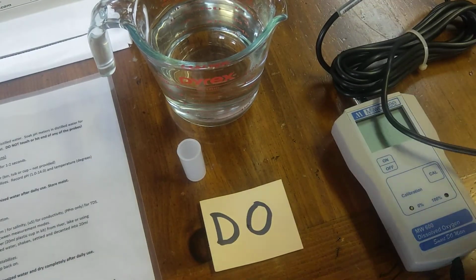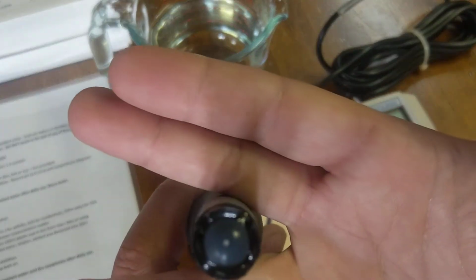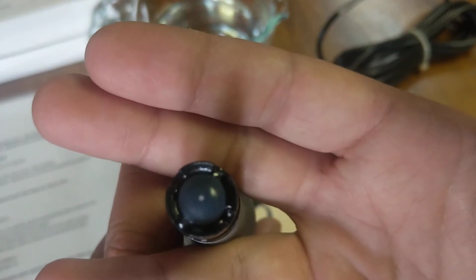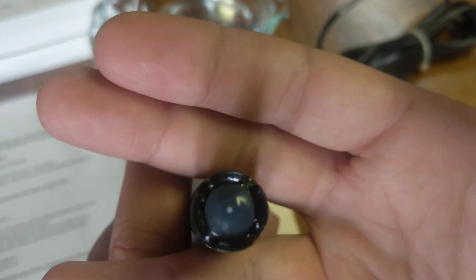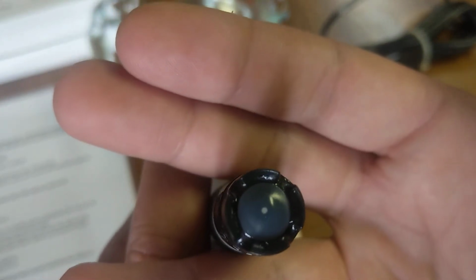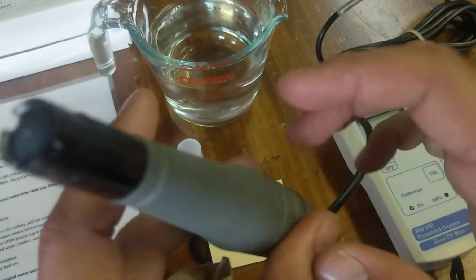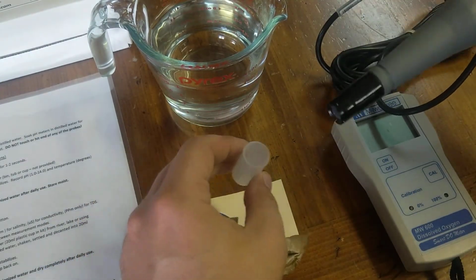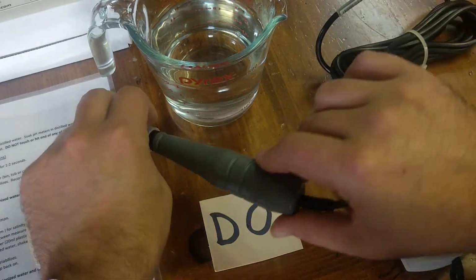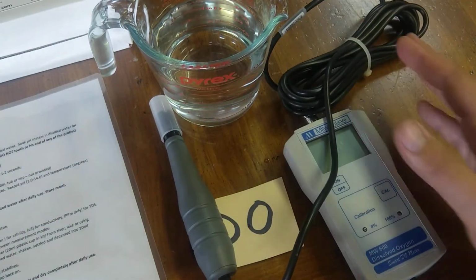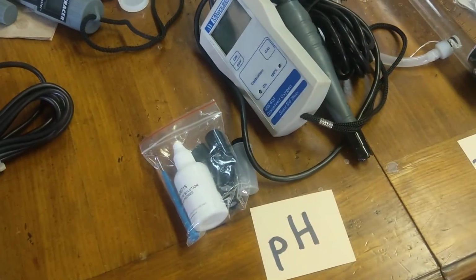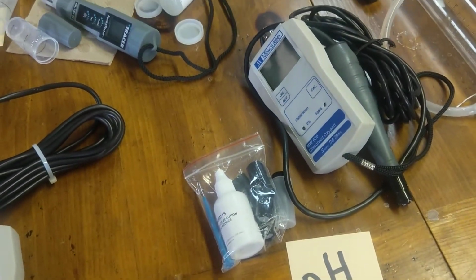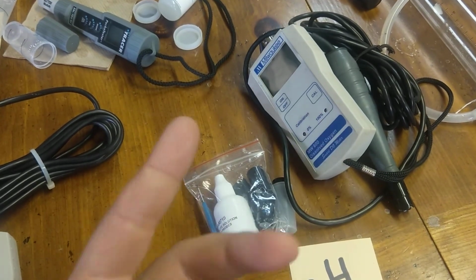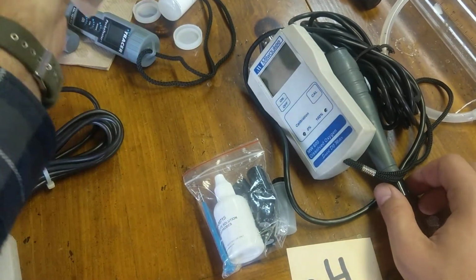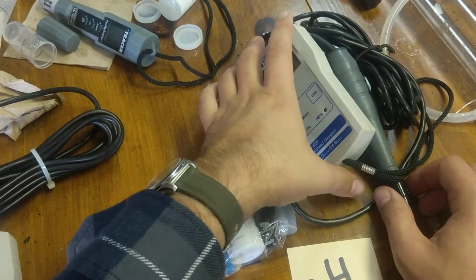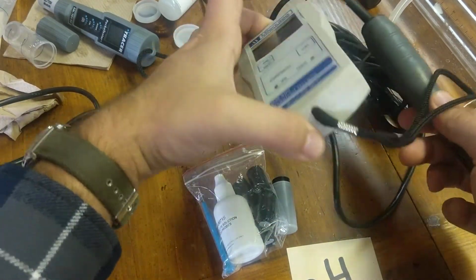Now, just for general maintenance, you want to make sure there's, again, no bubbles on the end here that is filled with that fluid. That fluid is necessary in order for it to continue. There's no bubbles in here. This is absolutely perfect, so we will have accurate readings. I'm just going to cap this to protect it for now and set this aside, because what we're going to be doing is setting one of these up to show the full procedure in case you do need to replace a damaged tip, or if there are any bubbles or anything like that, or just for general calibration.